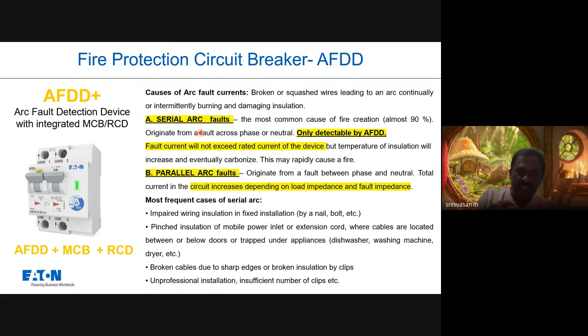So for any serial arc or parallel arc happening inside the final DB level for any specific circuit, we recommend putting this arc fault detection device. This arc fault detection device can also do the function of an MCB. That means it can also give overload and short circuit protection. Also, it can give earth leakage protection as well.